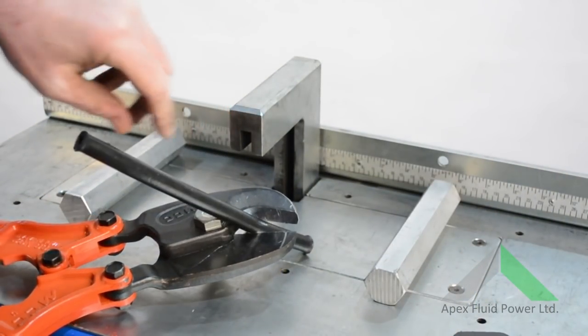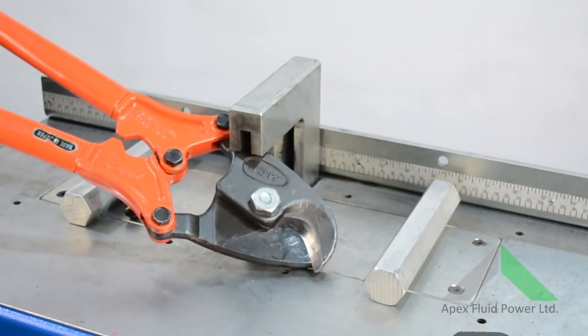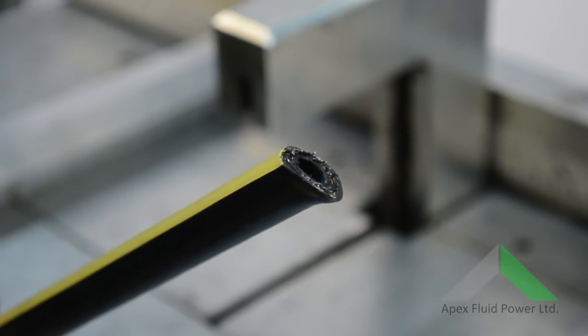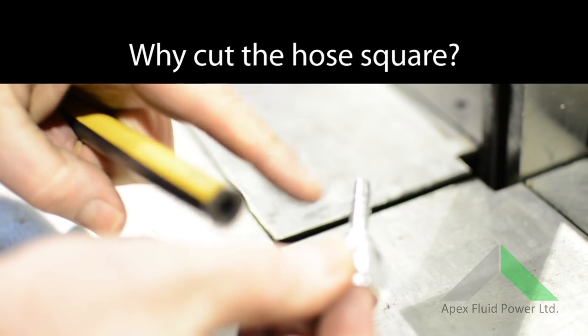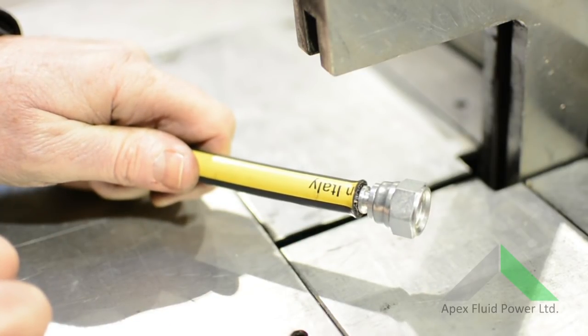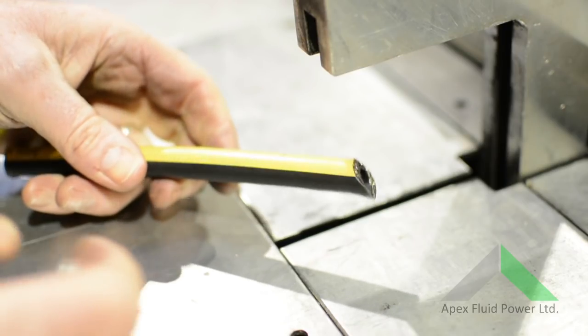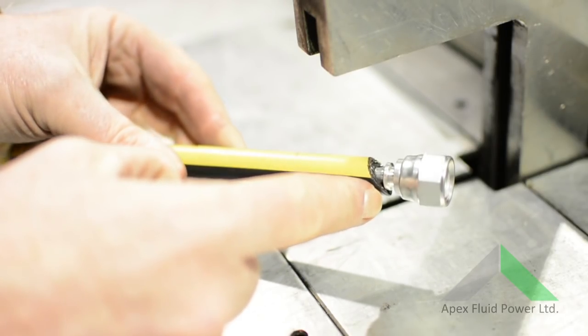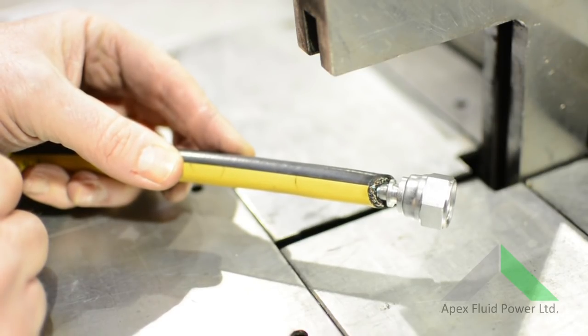A common tool often used is bolt cutters or chop saws, which give a rough distorted cut. Shown here with an ideal straight cut, we can push the fitting onto the hose ensuring the collar bottoms out on the square edge. If we had used the cut from the chop saw or cutters, the fitting will bottom out early, causing a leak when the hose is fitted. This will obviously be exaggerated on larger bore hoses such as multi-spiral lines.